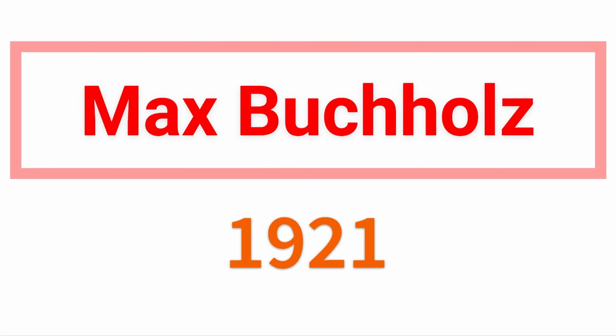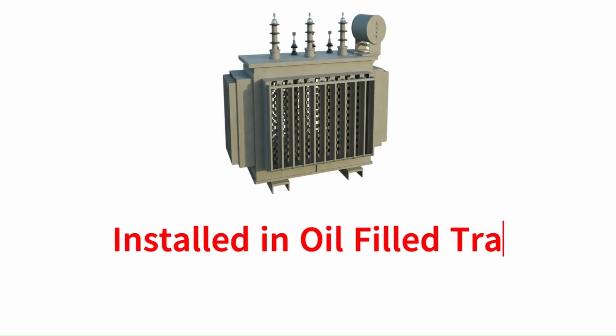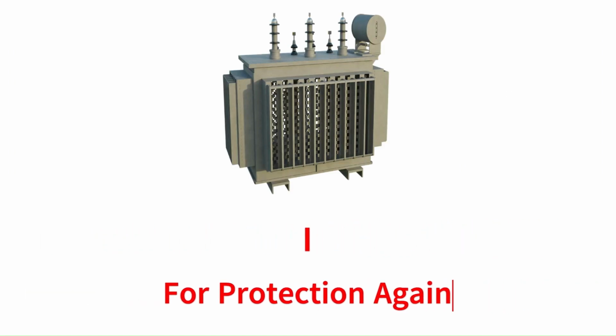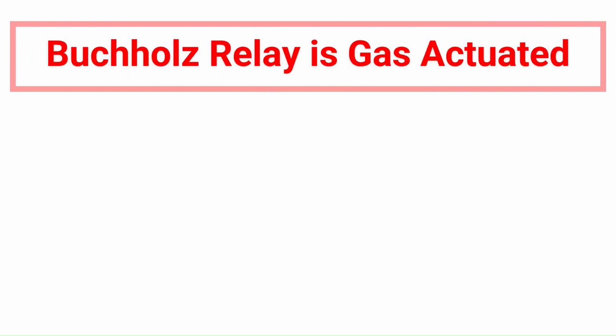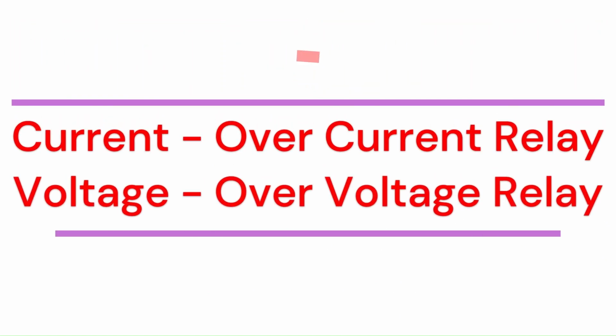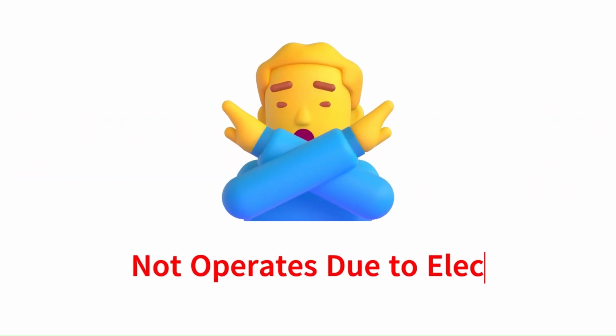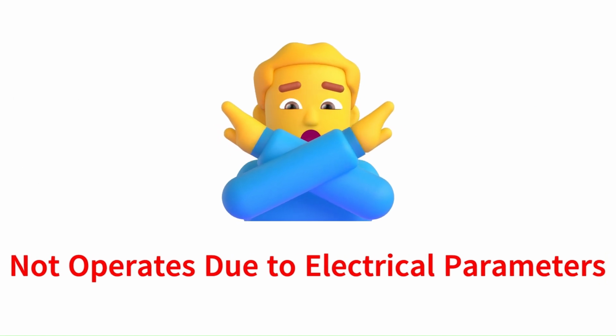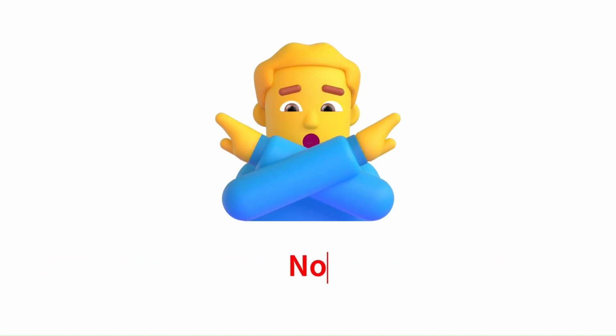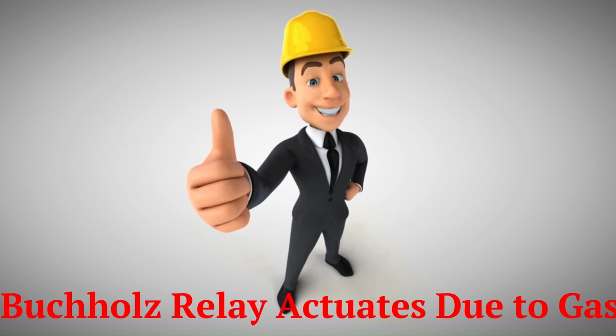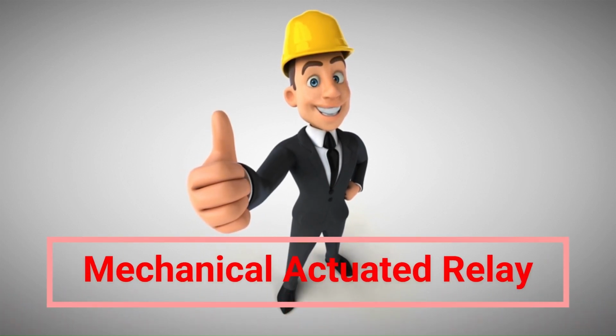Buchholz relay was invented by Max Buchholz in 1921. It is installed in oil-filled transformers for protection against all kinds of faults. The relay is gas actuated. That means it requires gas for its operation. Just like current is required for the operation of overcurrent relay and voltage is required for the operation of overvoltage relay, Buchholz relay does not operate due to any electrical parameters. It actuates only due to gas. Therefore, it is also called a mechanically actuated relay.